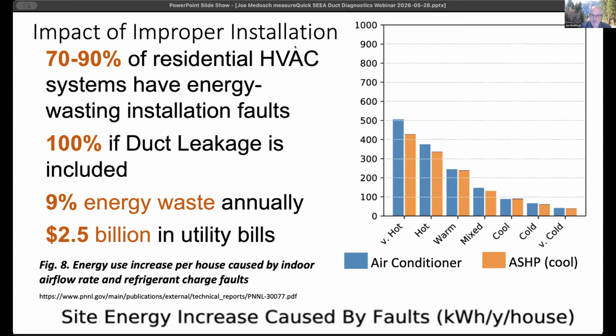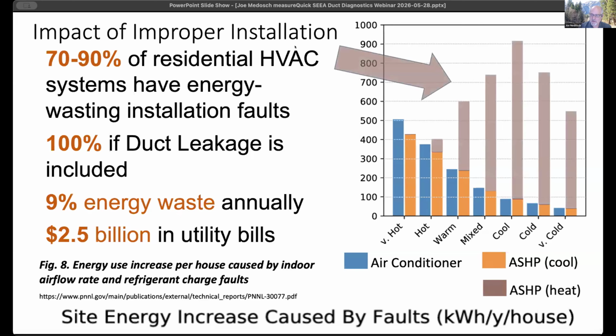And this is actually the illustration on the right is just regular air conditioners and air source heat pumps in cooling mode, right? Let's elaborate here. So if we go forward, this is actually air source heat pump in heating mode. These are the things that we're failing to try to convert this. Oh, let's go into heat pumps, heat pumps, heat pumps. And many people are not doing a good enough job of diagnosing the existing system they have or confirming that what they're installing is installed correctly. And airflow is a major significant part of that. So the whole duct concept has got a lot to wrap around.